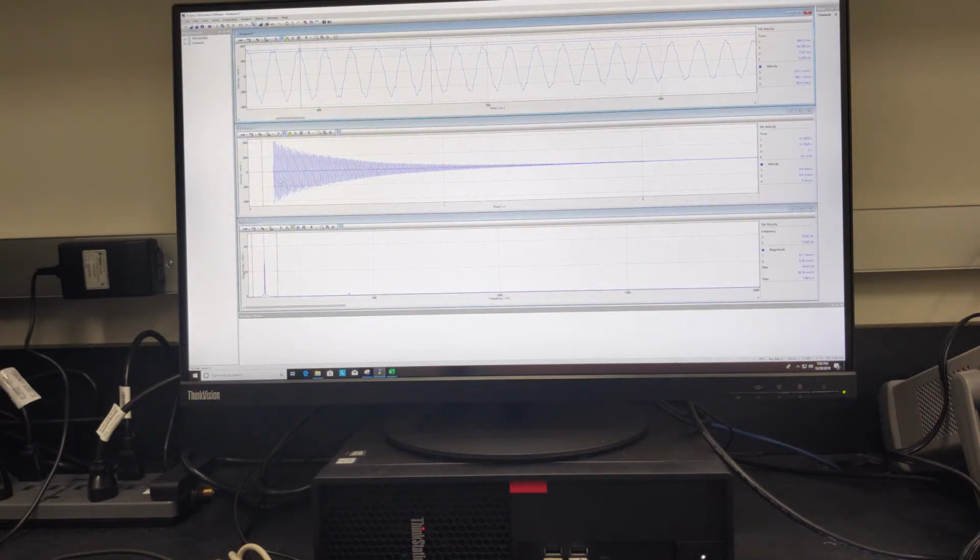In the time domain, choose the band cursor to measure the maximum velocity magnitude. Simply drag the cursors, one to the very beginning, the other to the ring down. Then the red cursor will auto fit the maximum velocity. Lastly, check all the values in the frequency domain and time domain. Record them into the spreadsheet for analyzing later.